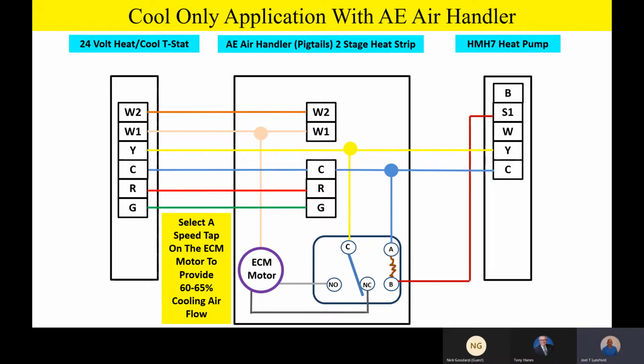The other thing to please consider when you're setting up your airflow, if you're in a humid environment, make sure that you consider setting your airflow instead of 400 CFM per ton. I've already got approval from the factory, one of our factory engineers, to say what I'm about to say. If you are not going to use the airflow reduction on a 2-wire system and no relay, then what we're going to recommend you do, if you're in a humid environment, is go ahead and reduce that airflow to 350 CFM per ton to give you a little bit more dehumidification during run cycle.